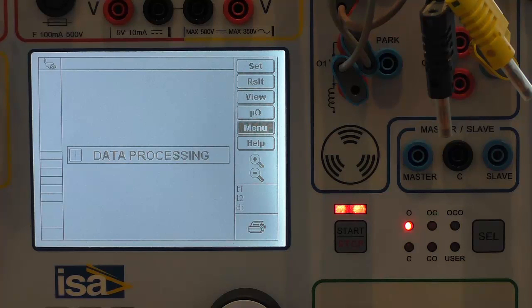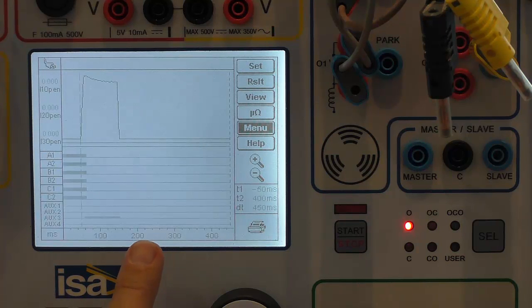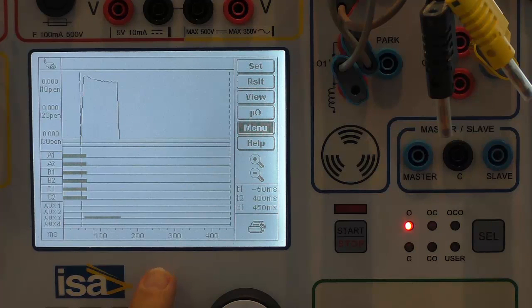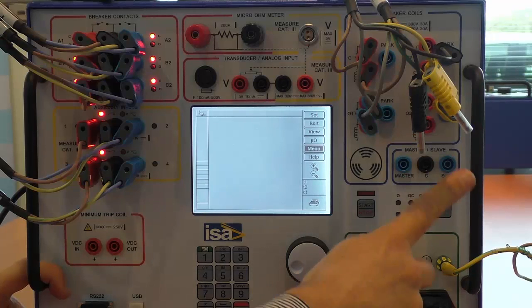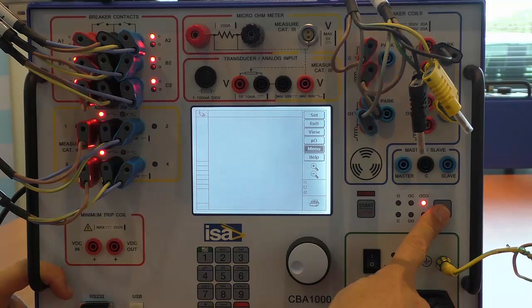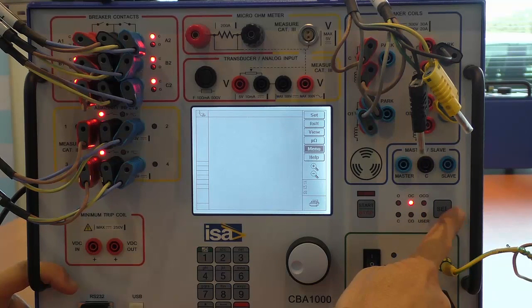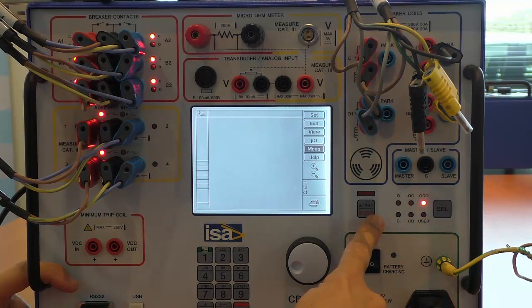Once the results start coming in, the system will display the result on the screen. So we can see the state of change of the main contacts and also some of the auxiliary contacts in this case. Additionally, on this screen you can view the coil current from the open coil in this case. In order to do a more complex operation, typically an open, close, open, you can select the operation via the select button and then initiate the operation via the start button.